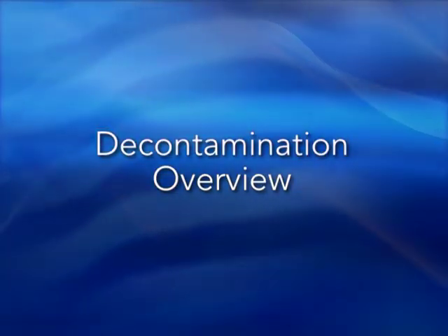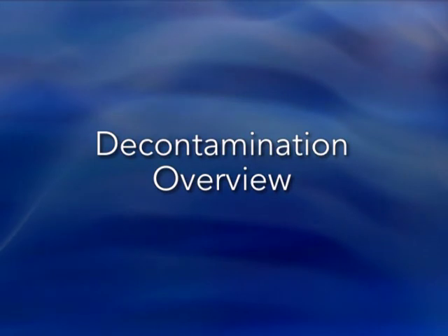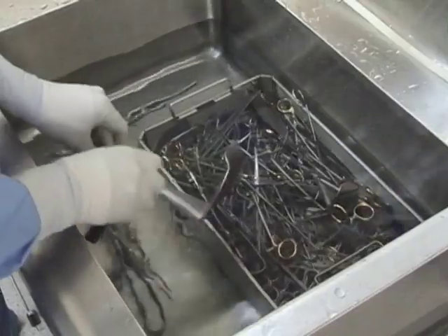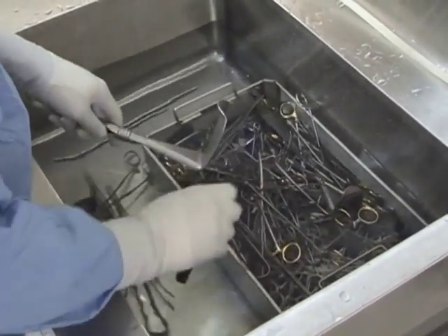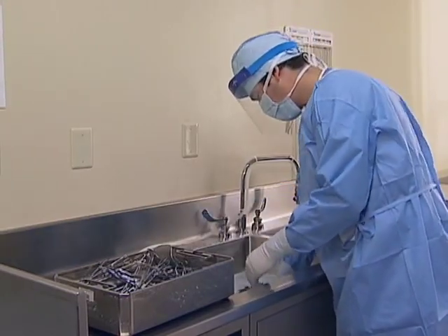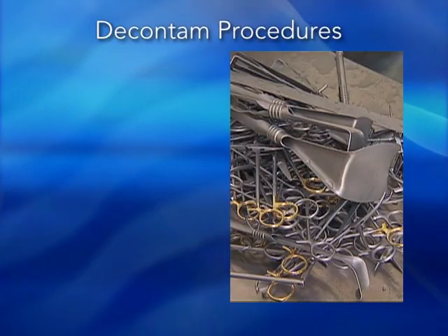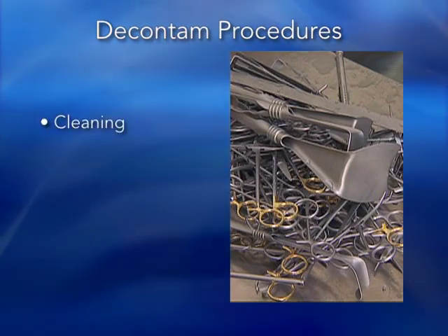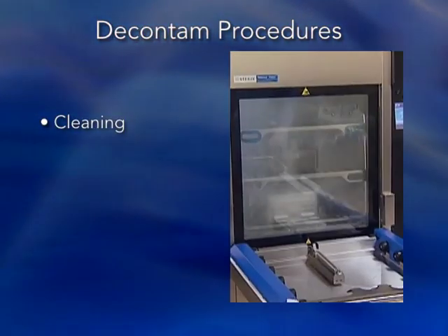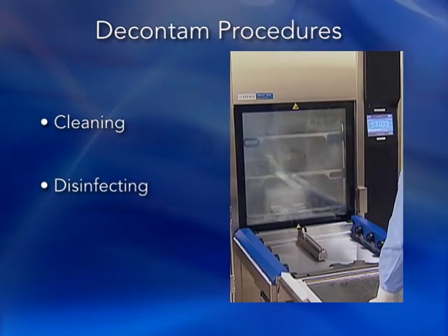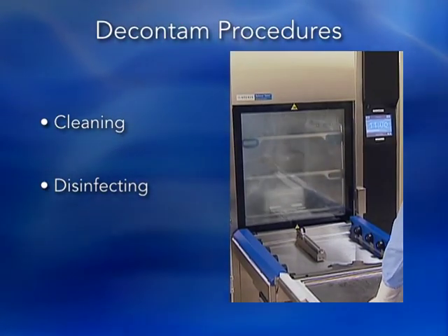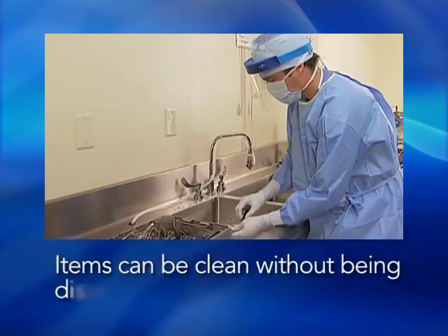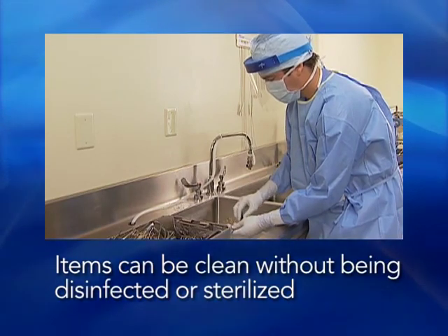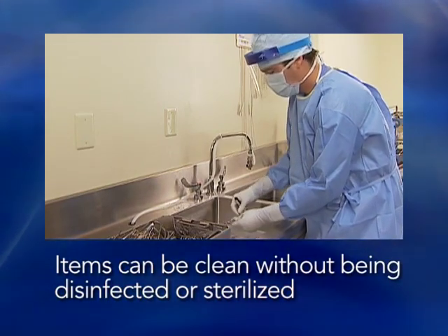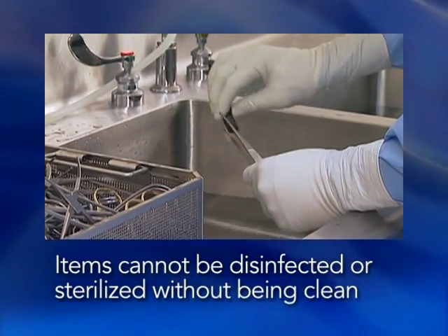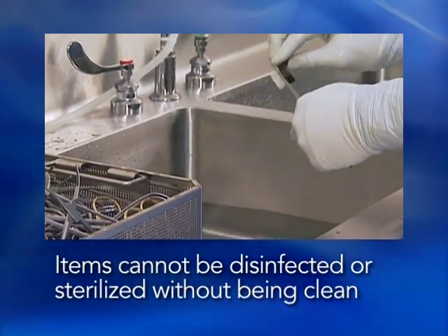Decontamination is a process that physically, thermally, or chemically removes potentially infectious organisms from surgical instruments and devices, making them safe for handling, use, or disposal. Decontamination consists of 2 main procedures: cleaning surgical instruments and devices, then disinfecting them for safe handling before they are further processed, and then terminally sterilized. The cleaning step is very important because an item can be clean without being disinfected or sterilized, but it cannot be disinfected or sterilized without first being clean.